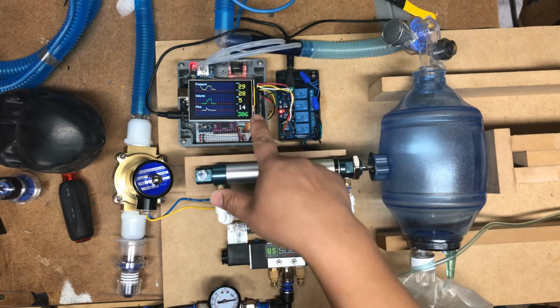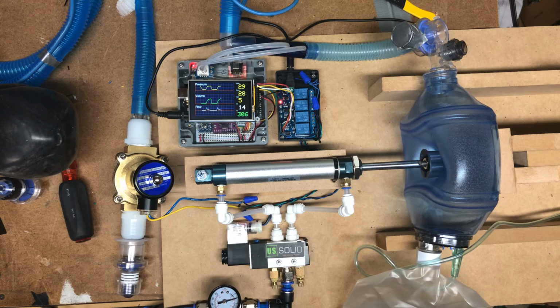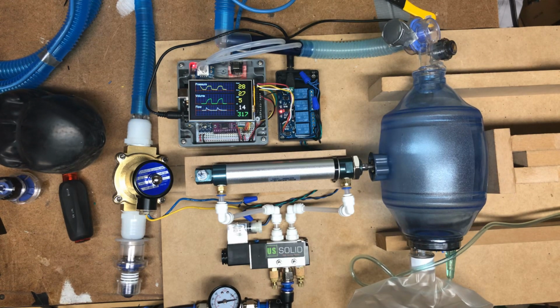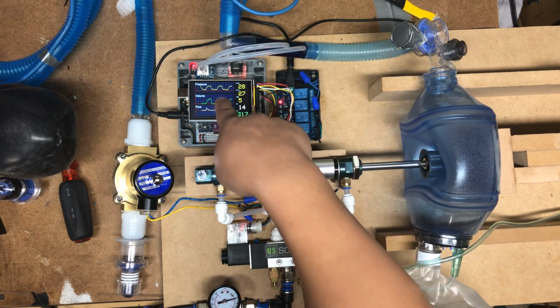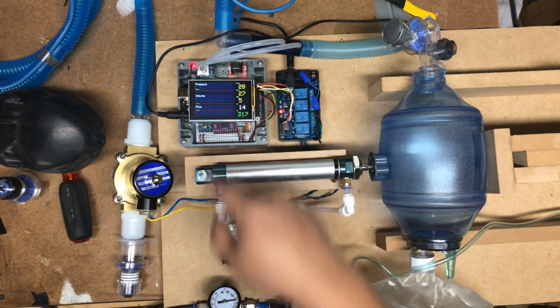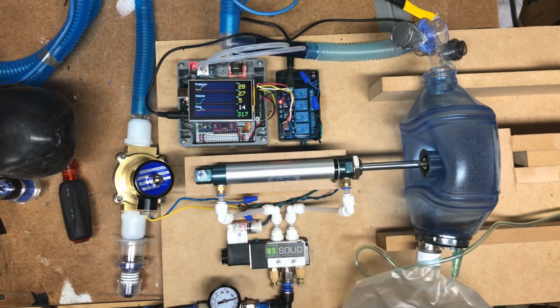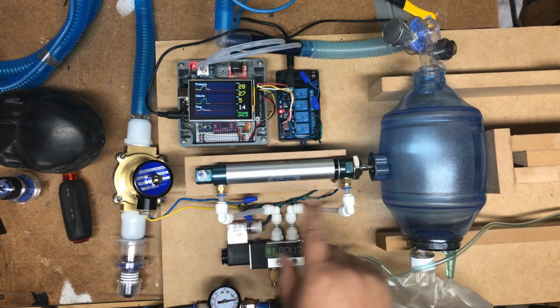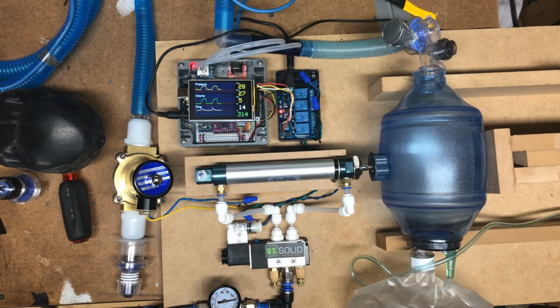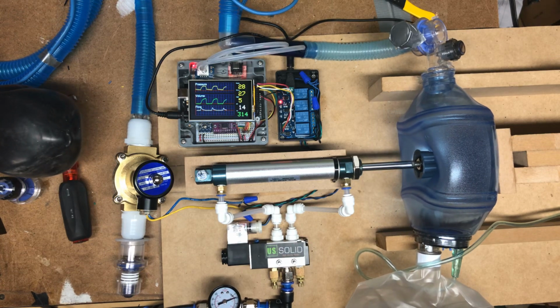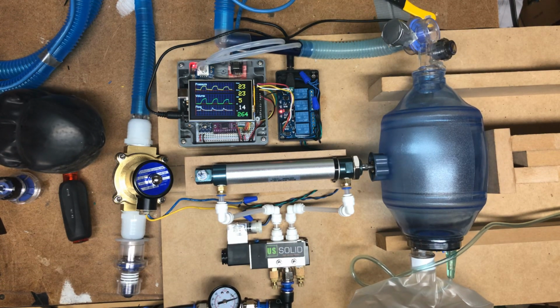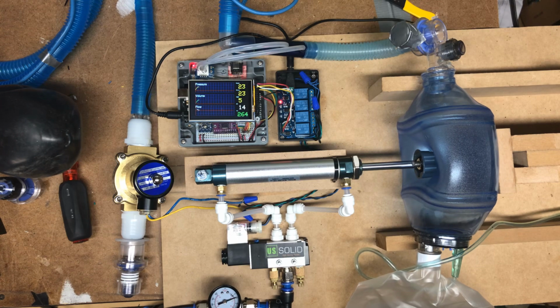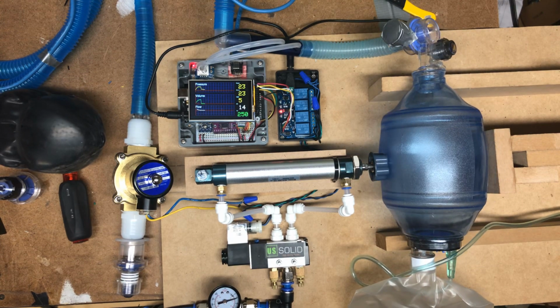So here you can see that I currently have it set at 29 centimeters H2O in pressure control mode, and it ramps up to 28, and the peak and the plateau pressures are very close because it's automatically modulating the speed of the piston to maintain that pressure. I can turn it down some. We can go to a lower pressure. So this is pressure control mode at 23.